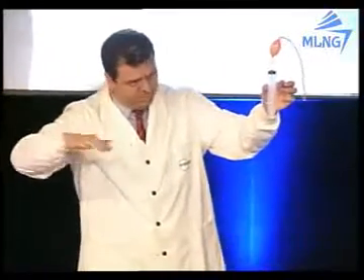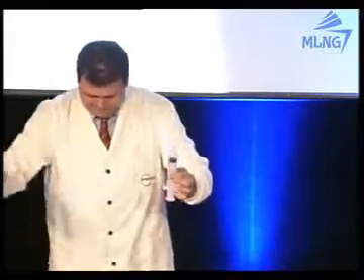So if we want to control the pressure during the filling process, one thing we can do is to remove this gas and put the gas in another place. For example, venting to the atmosphere or another vessel. Yes, we don't like that, okay? Or we can go to a boil-off compressor and recondense it, okay?